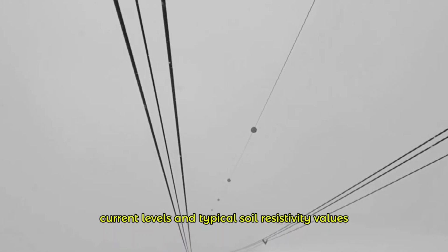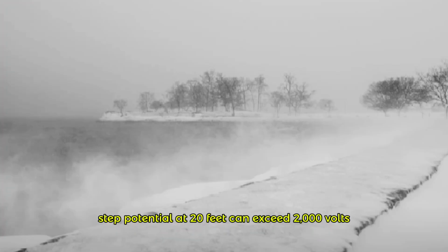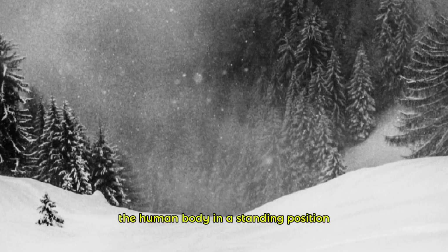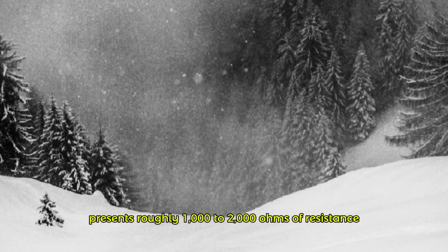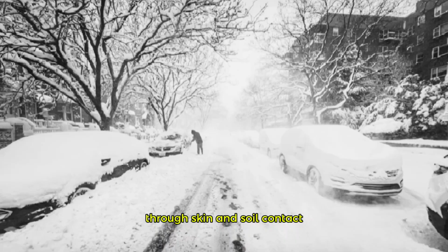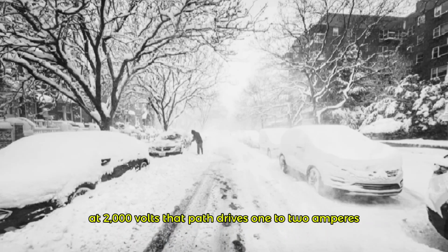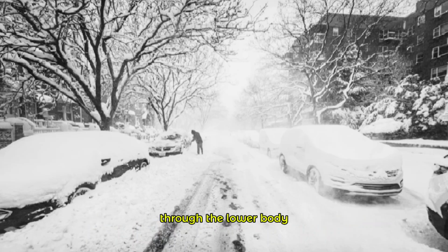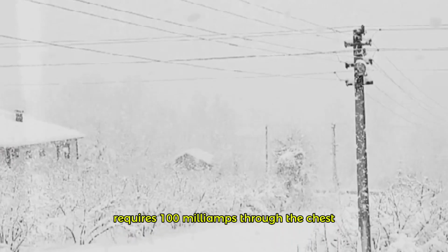At 150 kilovolt fault current levels and typical soil resistivity values measured in the field, step potential at 20 feet can exceed 2,000 volts across that 1 meter gap. At 15 feet, it is higher. The human body in a standing position, current flowing foot to foot through the lower legs and across the pelvis, presents roughly 1,000 to 2,000 ohms of resistance through skin and soil contact. At 2,000 volts, that path drives 1 to 2 amperes through the lower body. Ventricular fibrillation in a human being requires 100 milliamps through the chest, sustained for more than 1 second.